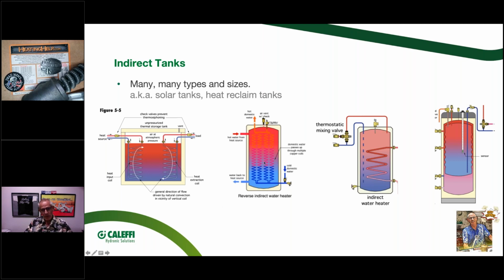One of the most interesting tanks out there as far as indirect tanks are these reverse indirect tanks. You've probably seen this. Basically what we're doing is putting the boiler water in the tank, and running the domestic water through the copper coils. Again, the key is having a lot of heat exchange surface.